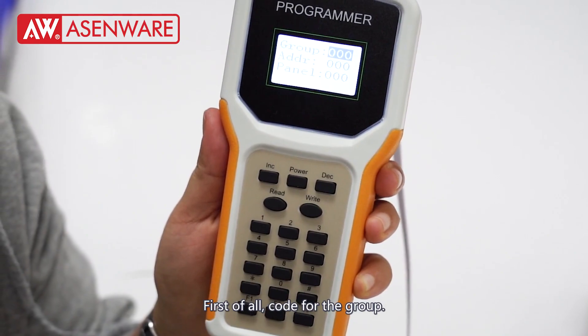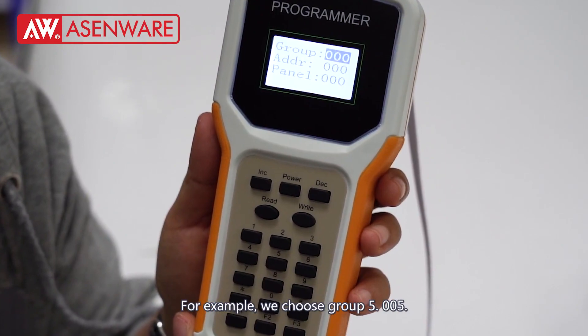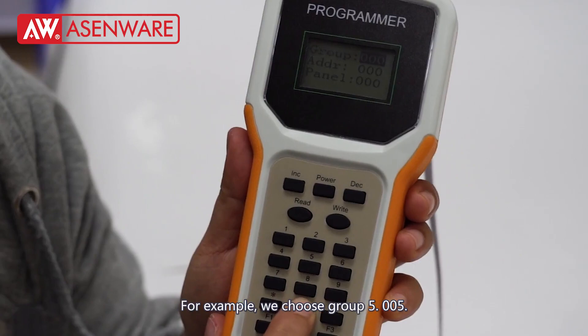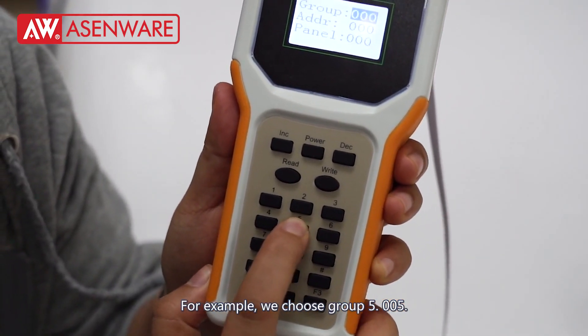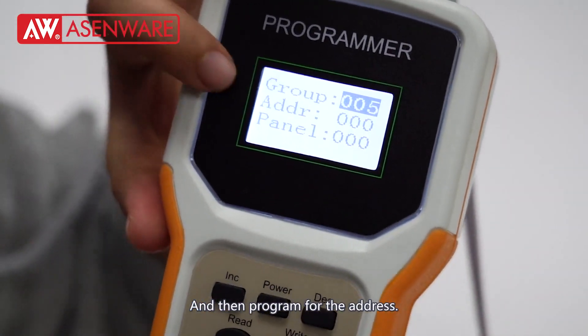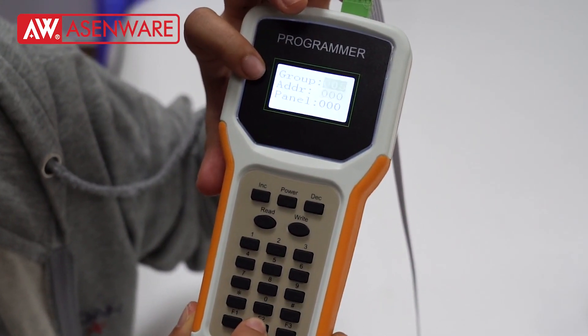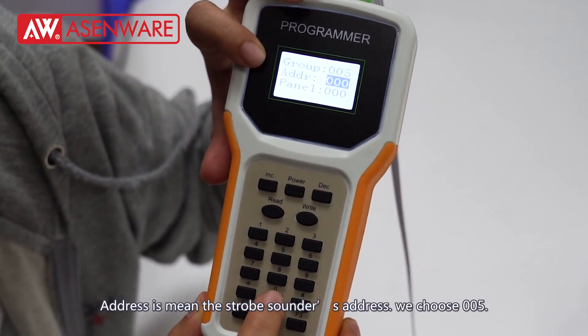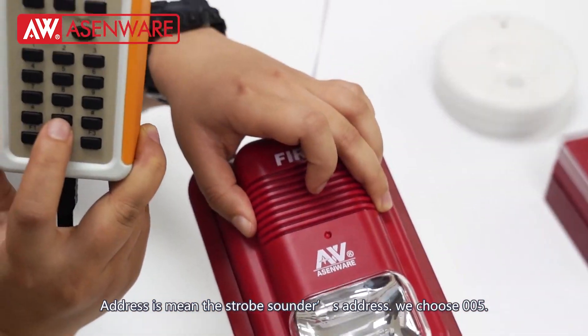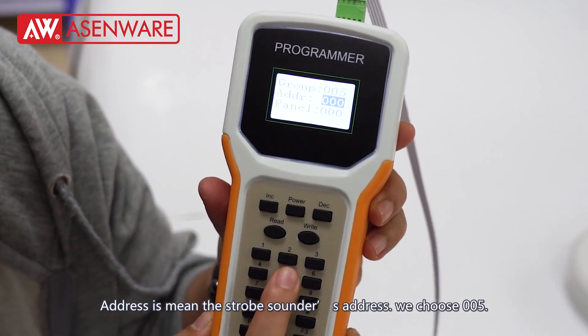First of all, code for the group. For example, we choose group 5: 0, 0, 5. And then program for the address. Address means the strobe sounder's address. We choose address 0, 0, 5.